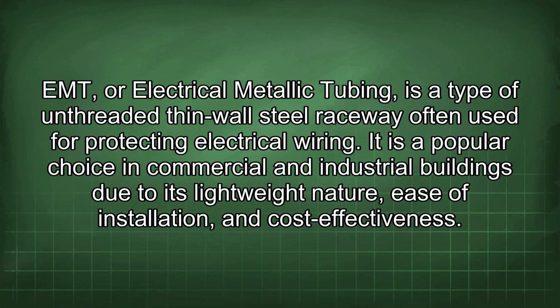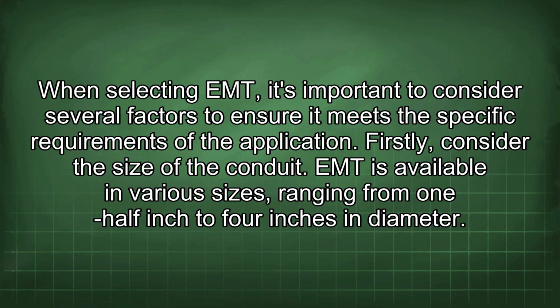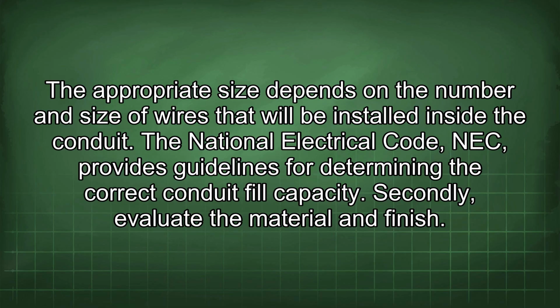EMT, or electrical metallic tubing, is a type of unthreaded thin-wall steel raceway often used for protecting electrical wiring. It is a popular choice in commercial and industrial buildings due to its lightweight nature, ease of installation, and cost-effectiveness. When selecting EMT, it's important to consider several factors to ensure it meets the specific requirements of the application. Firstly, consider the size of the conduit. EMT is available in various sizes ranging from 1/2 inch to 4 inches in diameter. The appropriate size depends on the number and size of wires that will be installed inside the conduit. The National Electrical Code (NEC) provides guidelines for determining the correct conduit fill capacity.